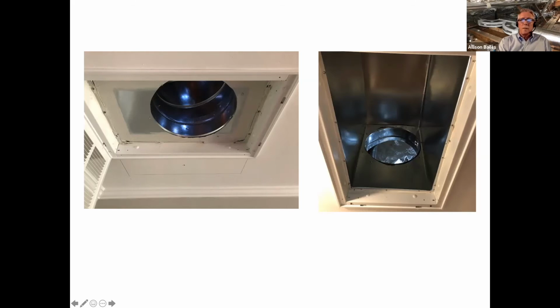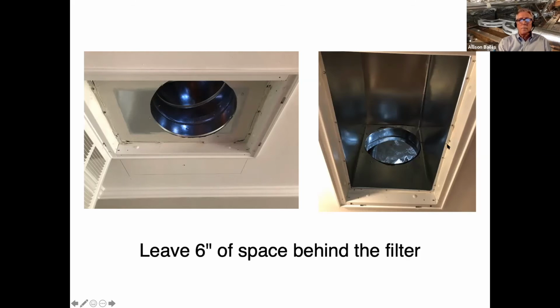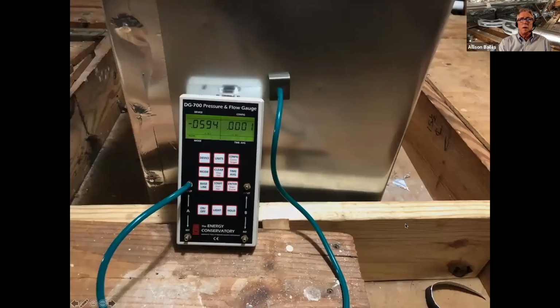So with that space, my pressure drop across the filter went from about 0.08 to about 0.06. So I got about a 30% decrease in my pressure drop just by putting this big box on the back of the filter, giving it more space. What that does, remember earlier I talked about turbulence being one of the factors that hurts your airflow. When you put a lot of space back there, it reduces the amount of turbulence that's happening in the airflow back there.